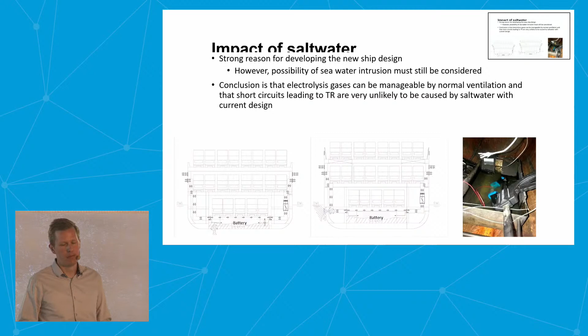It's not a rapid process. And then we have the risk of short circuit and thermal runaway, but that will require higher voltage than cell level. So it's very unlikely to happen on cell level. So you need some 100 of volts. And then we rely on external short circuit protection on module level as an important safety measure.